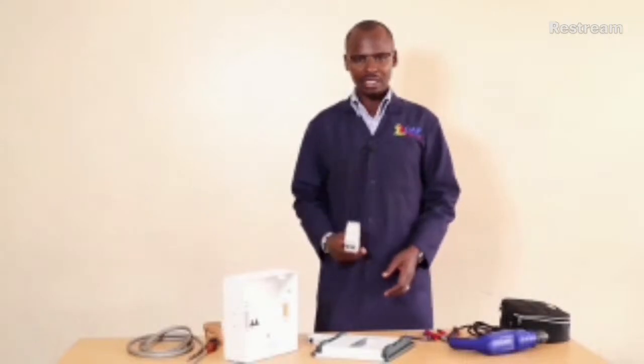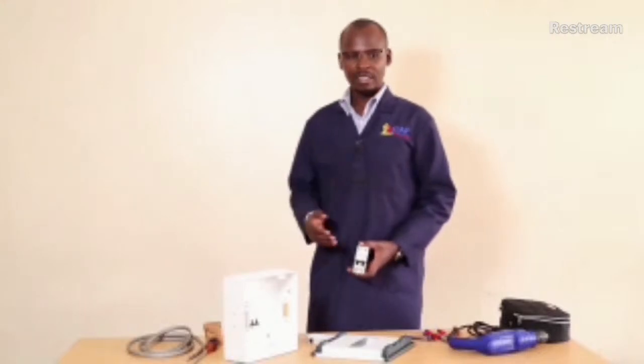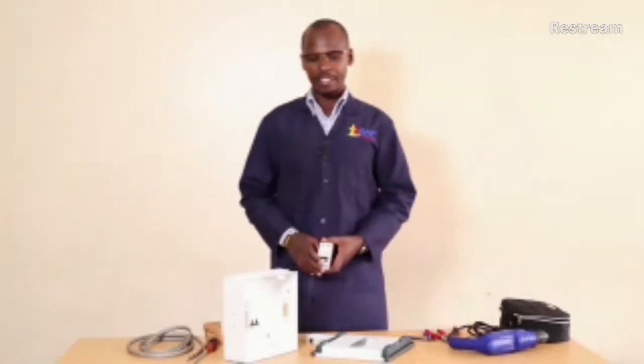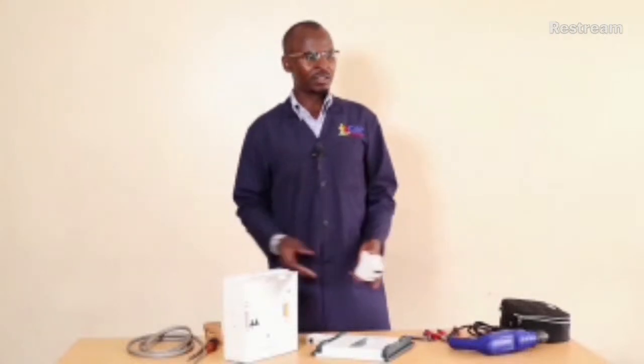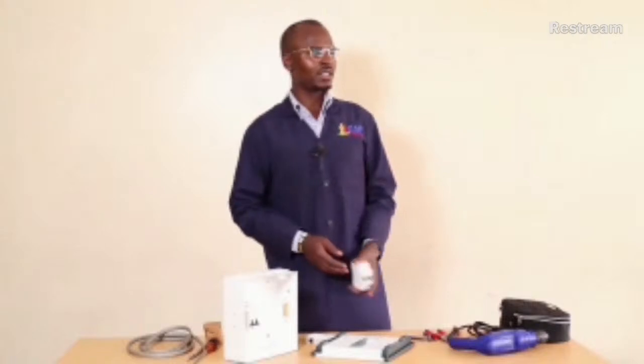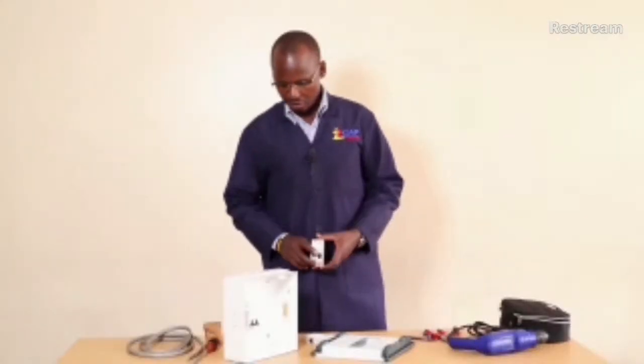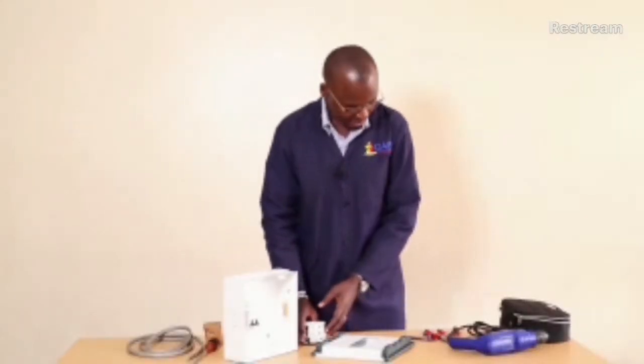So it is very important to understand that you use the right fuse or circuit breaker for the right line. In many cases, you have seen bulbs burning or blowing up in houses. The main reason why, to some extent, that happens, you will find that the rating of the line could be too much for the lighting system. If you maybe power your lighting system using 32 amps, you might have a scenario where bulbs just blow out without knowing what the problem is. So ensure that you use the right fuse for controlling the right system.